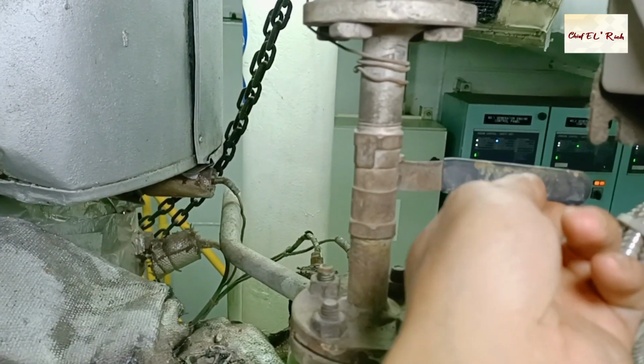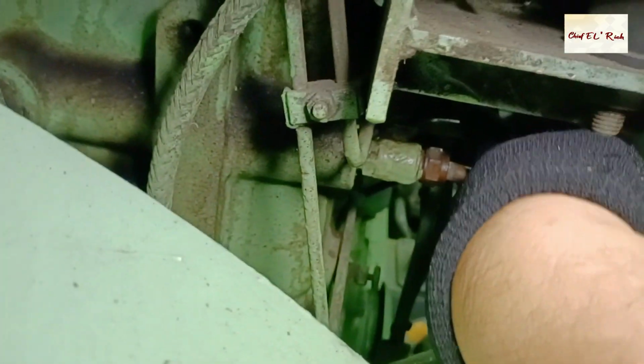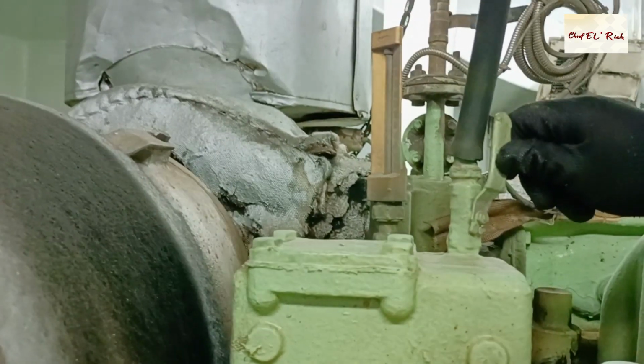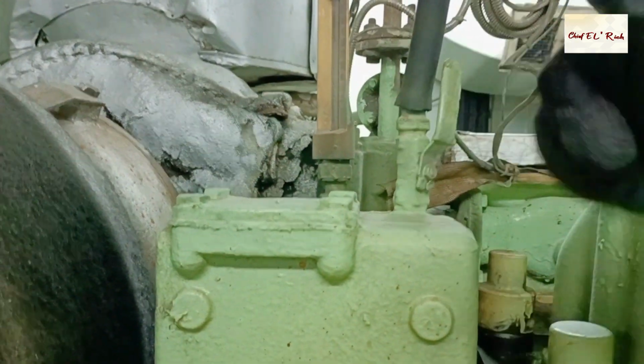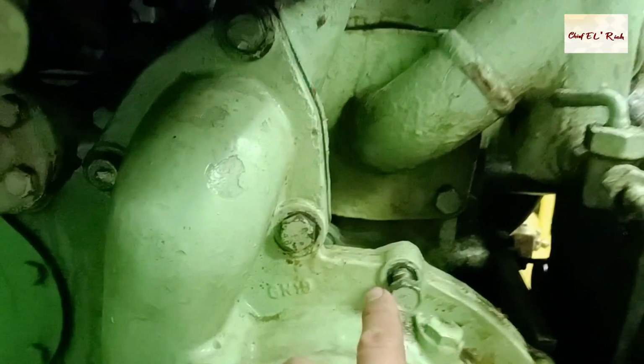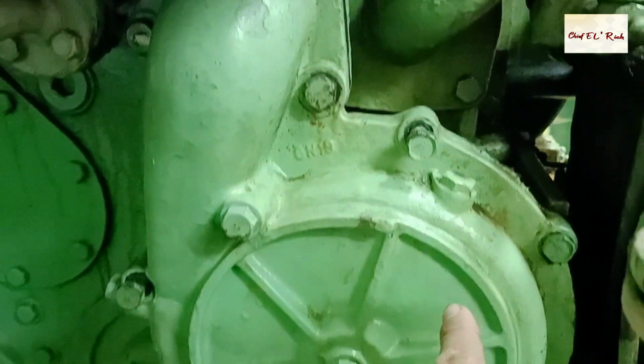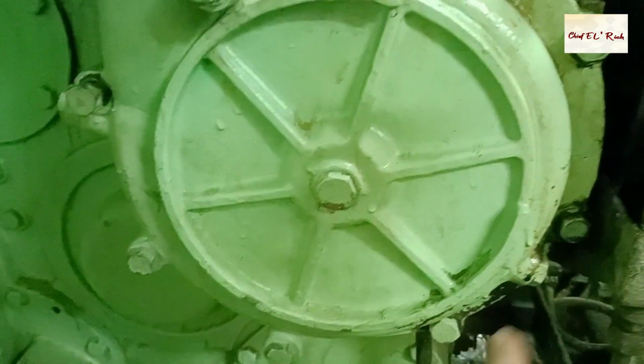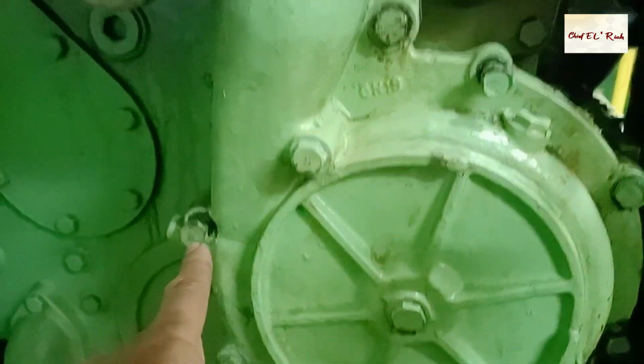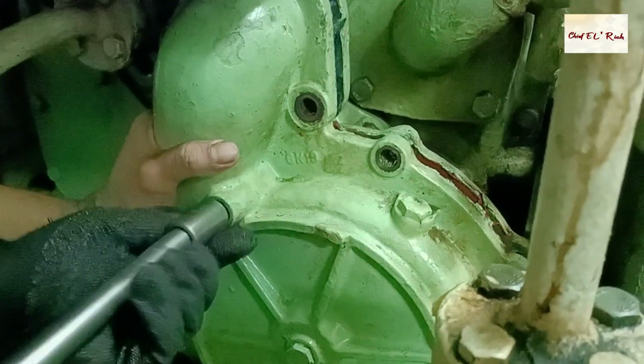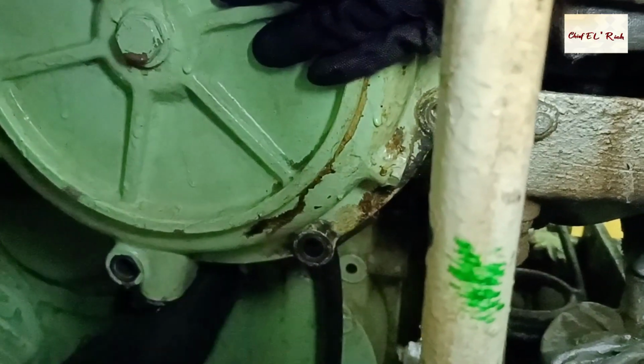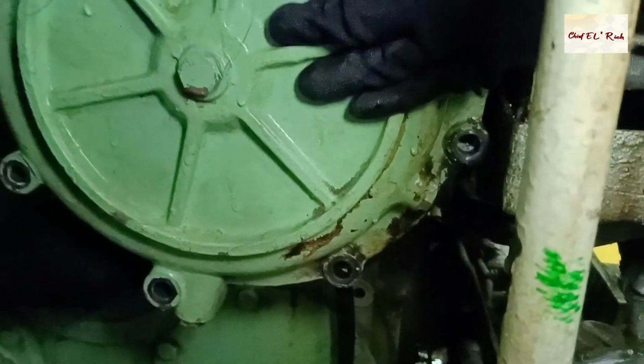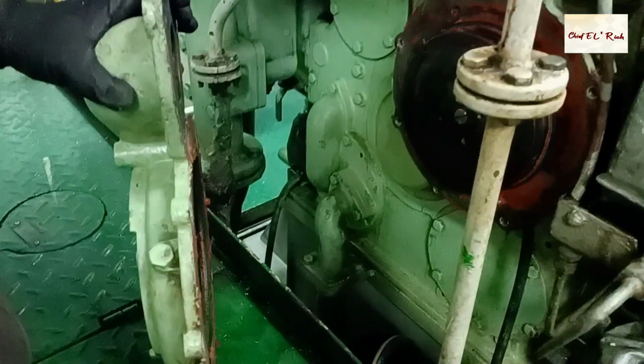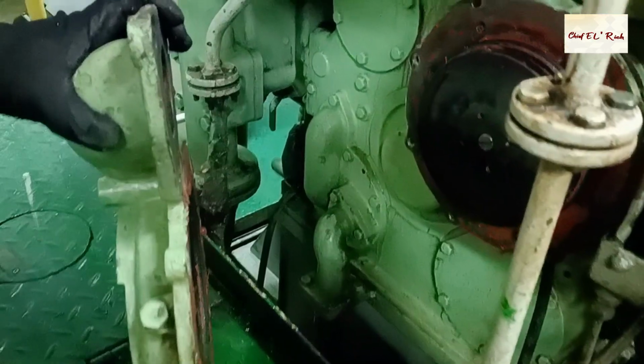and ventilation valve. Now we can start to open the drain valve and air purging valve so that the cooling water will drain faster. When the cooling water has completely drained, we can now start to overhaul the pump. Take out all bolts that hold the pump back cover. Then install the two pusher bolts in the threads located at the back to push the cover out. Once the back cover is taken out, you now have access to the impeller.